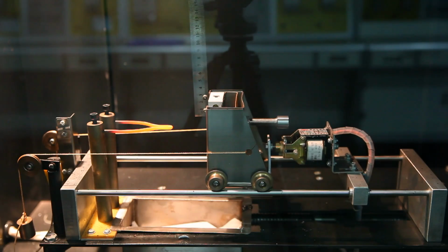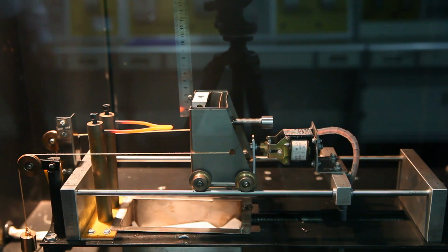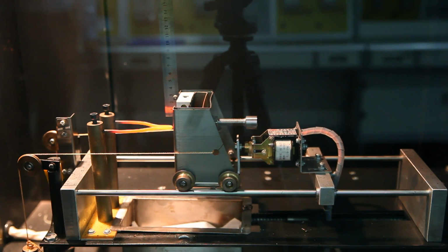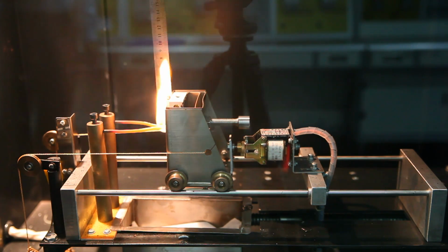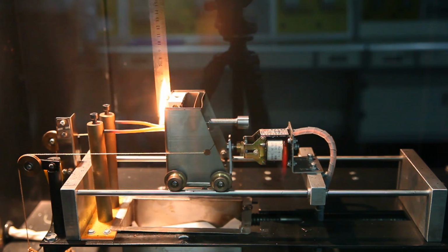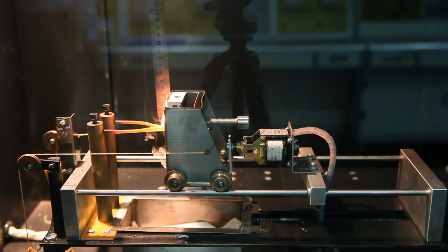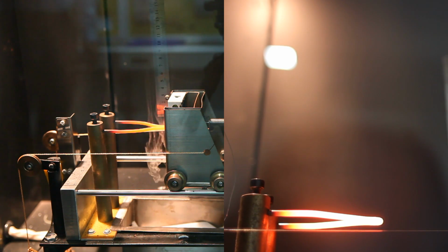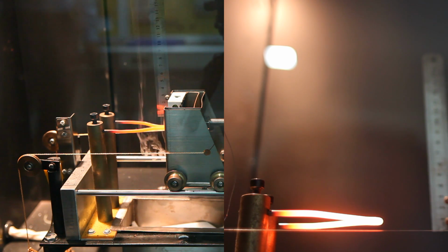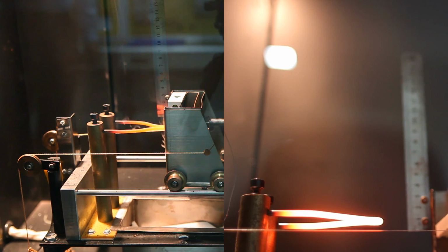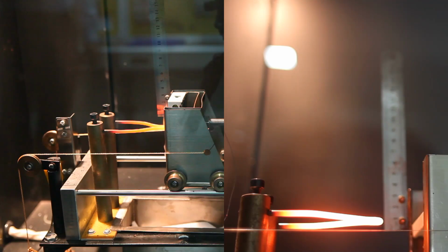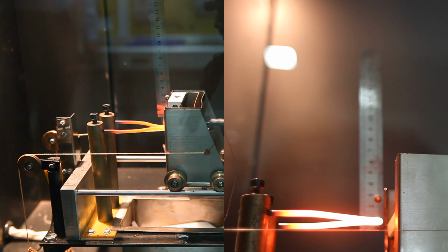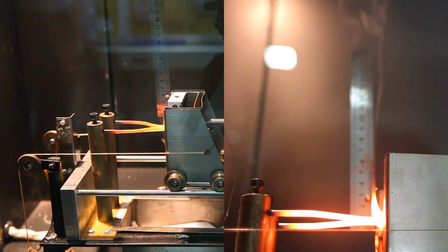The glow wire test is performed to prove the fire retardancy of the thermoplastic materials in contact with current-carrying parts or non-current carrying parts. The test procedures are as stipulated in IEC 60695-2-11. Temperature settings of the glow wire are preset before the mounted part under test comes into contact with the tip to be burned. The initiation of the test to the ending is fully automated as featured in the glow wire tester.